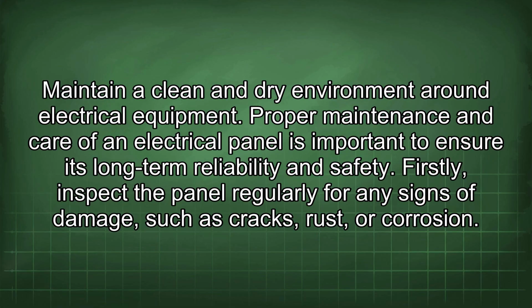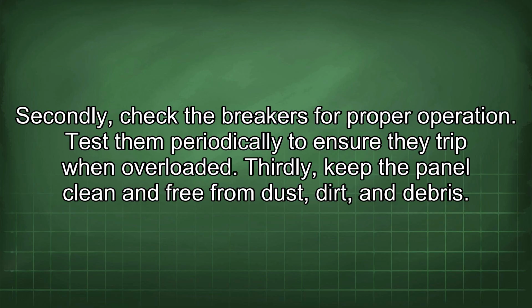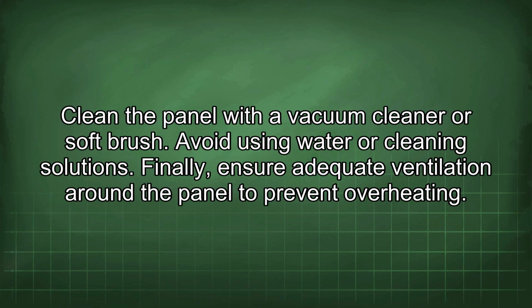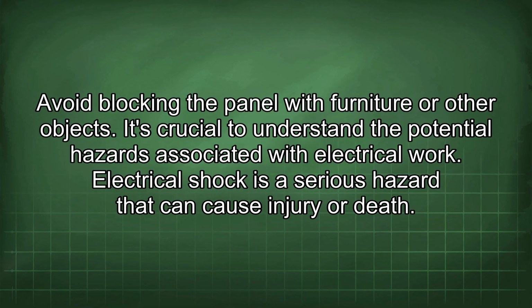Firstly, inspect the panel regularly for any signs of damage, such as cracks, rust, or corrosion. Secondly, check the breakers for proper operation. Test them periodically to ensure they trip when overloaded. Thirdly, keep the panel clean and free from dust, dirt, and debris. Clean the panel with a vacuum cleaner or soft brush. Avoid using water or cleaning solutions. Finally, ensure adequate ventilation around the panel to prevent overheating. Avoid blocking the panel with furniture or other objects.